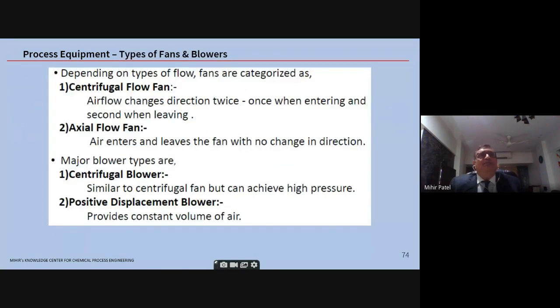Now types of fans and blowers. So these are the different types. Centrifugal flow fan is there. Axial flow fan is there. Axial flow fan is nothing but the exhaust fans we find in our house or warehouses, etc., which are very low head axial fans. Major blower types are centrifugal blower and positive displacement blower. Positive displacement blower is also called a roots blower, which is very highly used in pneumatic conveying applications.